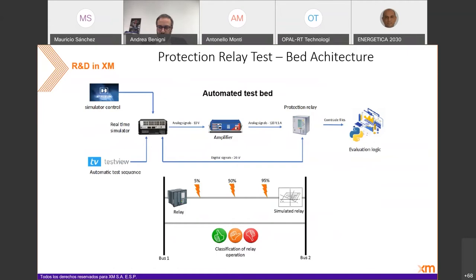Through Test View, another tool that allows us to automate the simulation, we can change from one scenario to another and change the type of fault. For example, we can change from an injection of a single phase to ground fault at 5% of the line to, in a matter of seconds, a fault in the middle of the line with another topology of the fault, and so on.